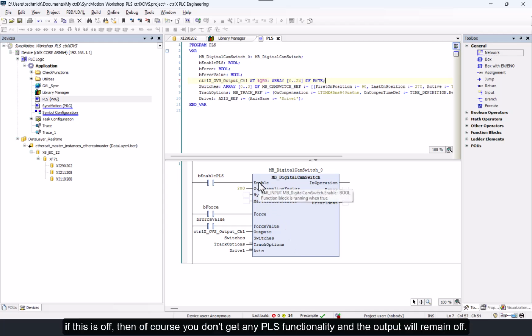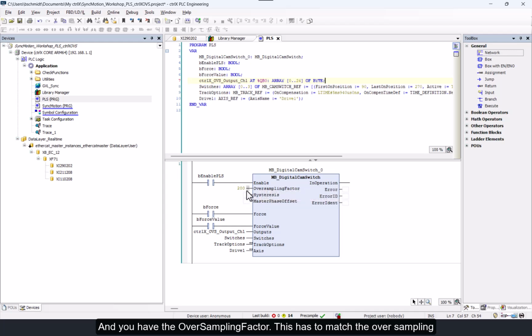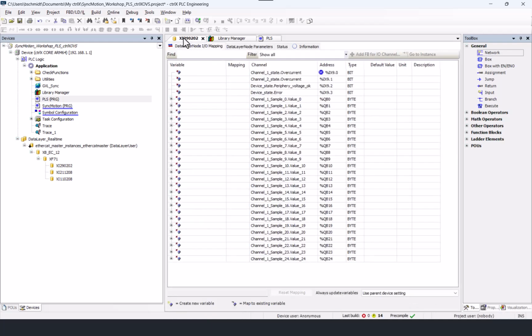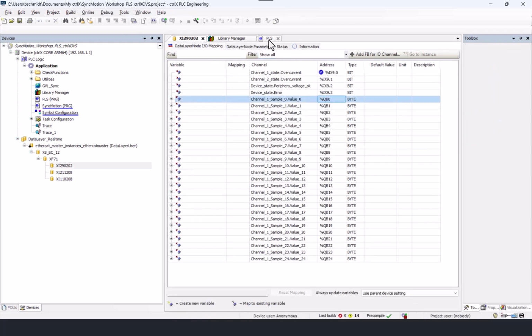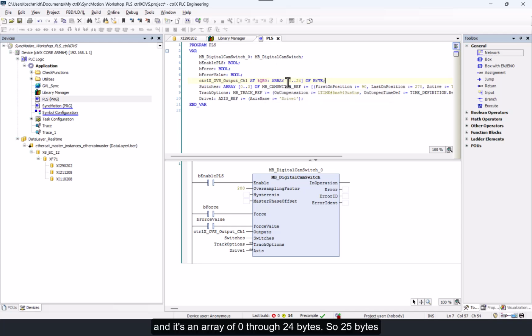First you have the enable. If this is off, then of course you don't get any PLS functionality and the output will remain off. Then you have the oversampling factor. This has to match the oversampling selection that you made for the module in the I/O Engineering. Let's jump down here. This is where you point the function block to the array of output bytes that are associated with whichever channel, channel 1 or channel 2, that you're going to apply this function block to. So here I made a declaration at a starting address of QB0. And it's an array of 0 through 24 bytes. So 25 bytes in total.